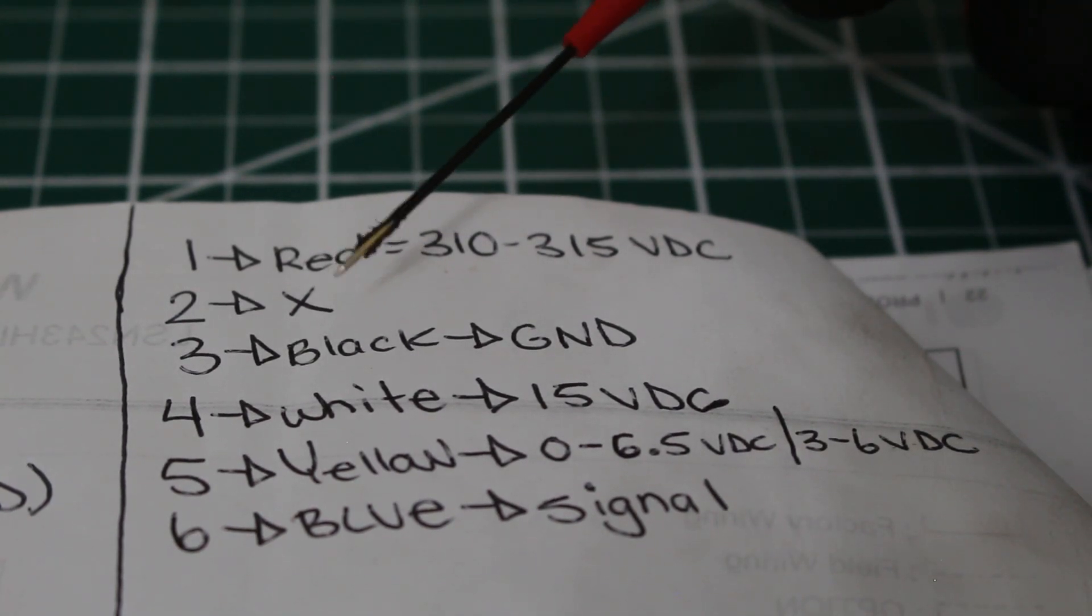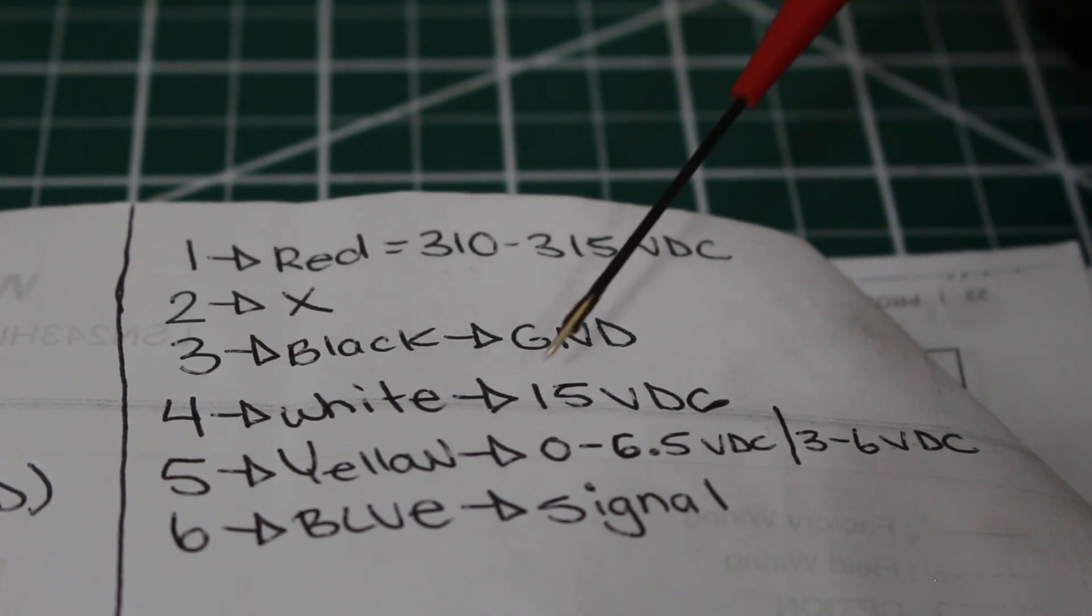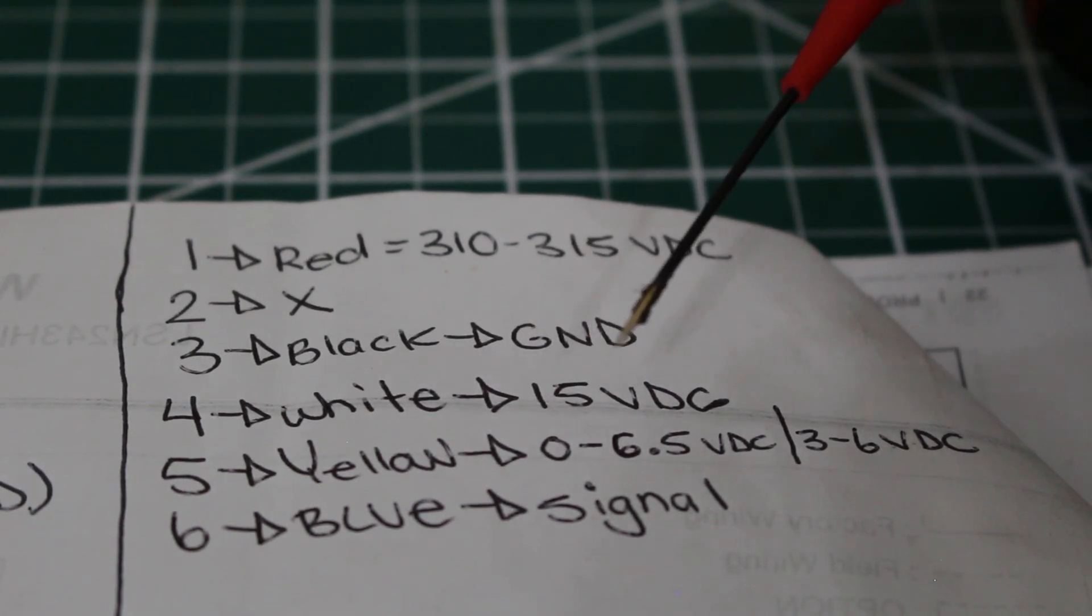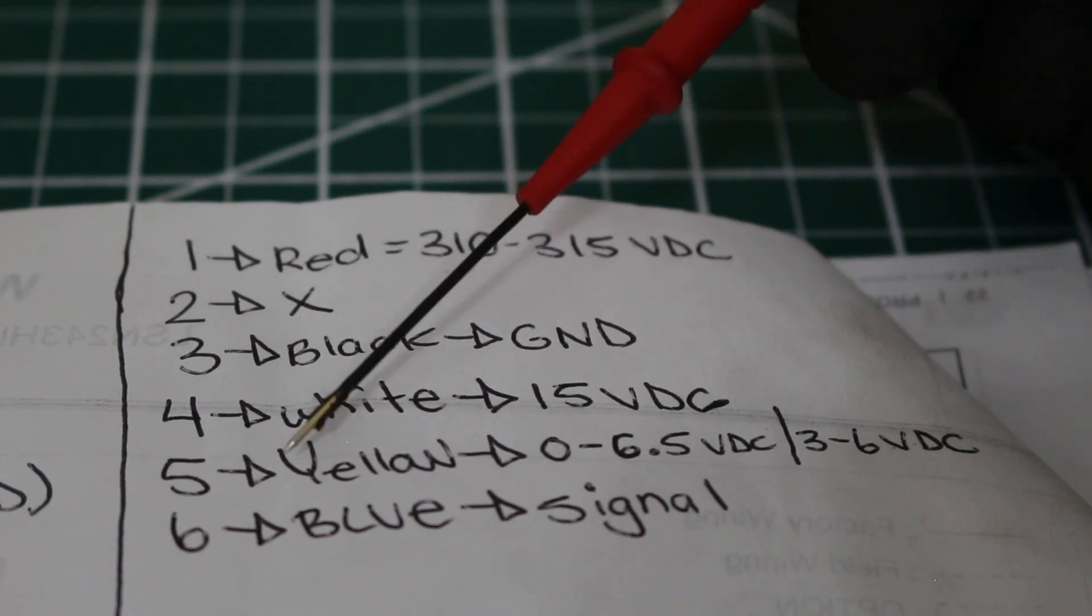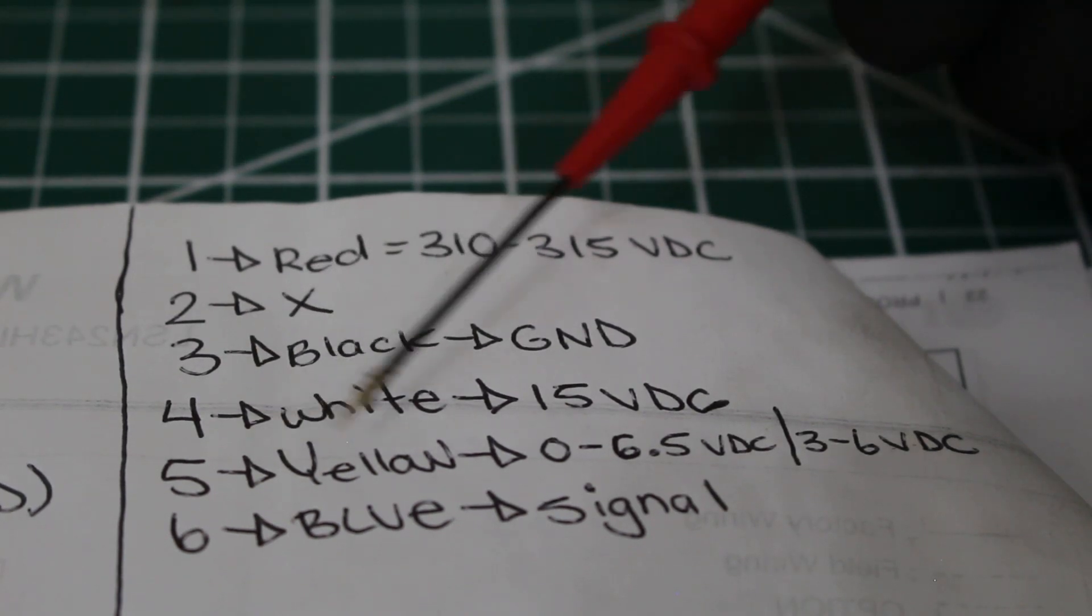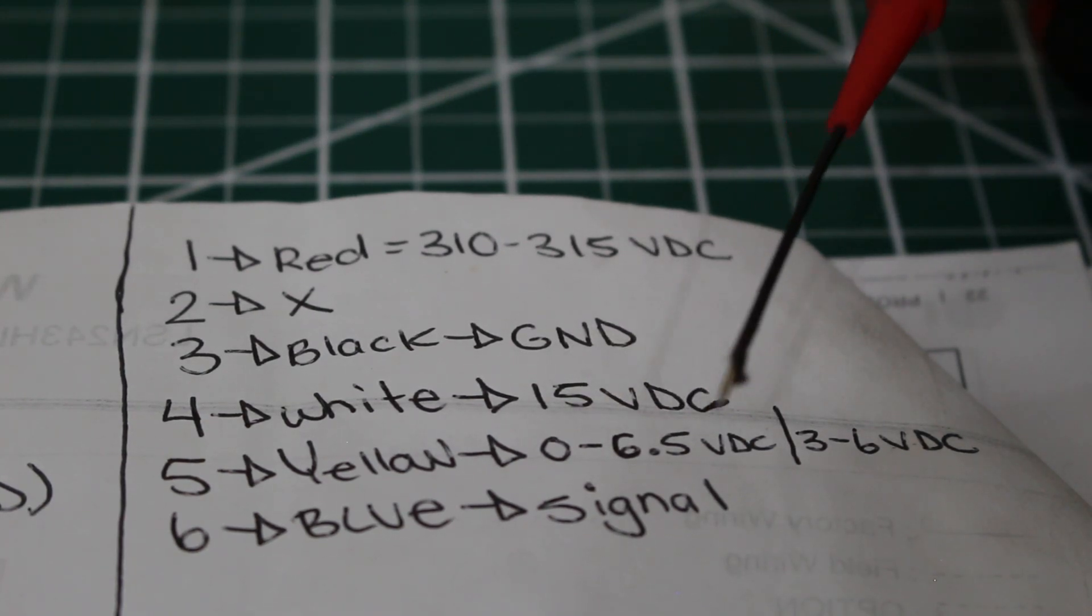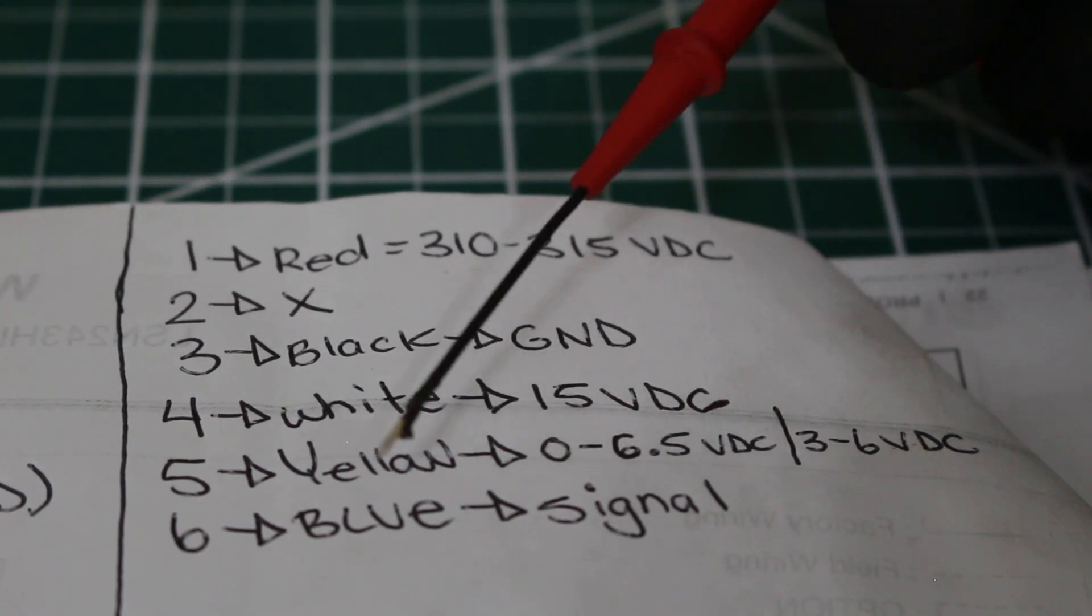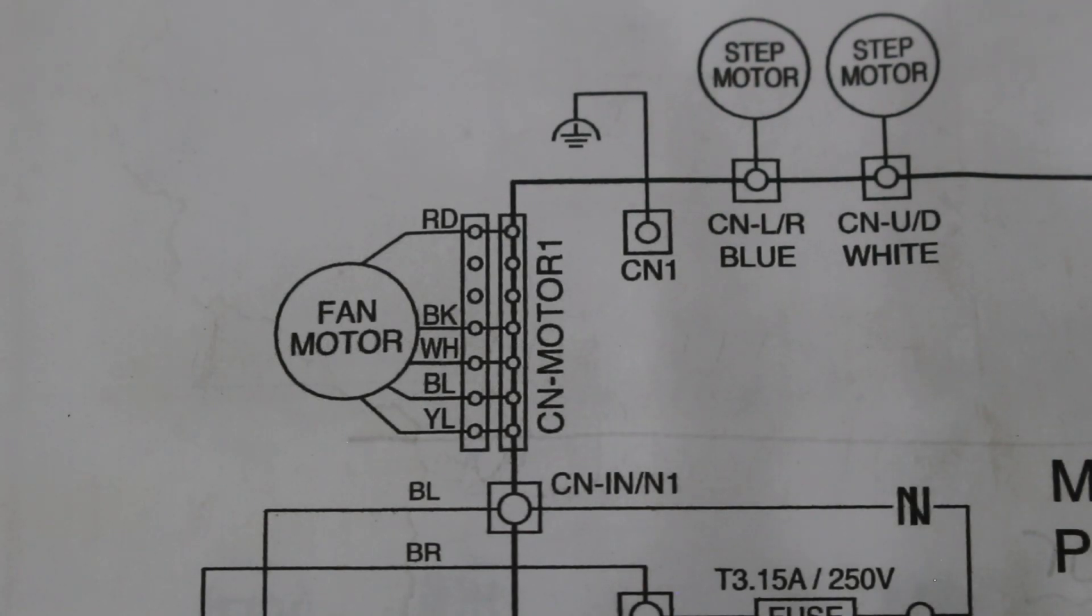Remember, terminal 2, there's nothing there. Then we're going to go from the black wire to 4. So between 3 and 4, you should be measuring around 15 volts DC. Then from black to yellow, 3 to 5, you should be measuring anywhere from 0 to 6.5 VDC. And between black and blue is your signal wire. There is no measurement for the blue wire. This is when you're checking voltage.